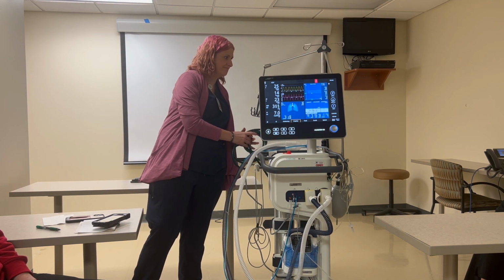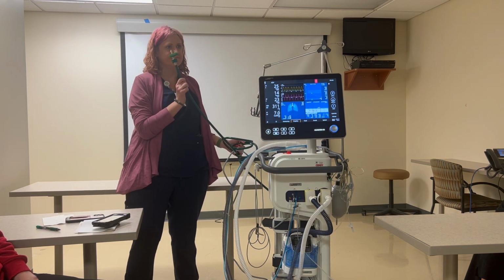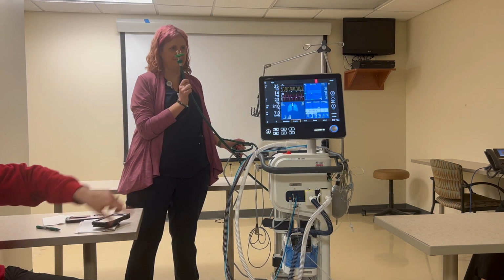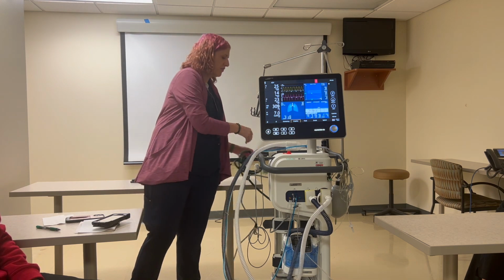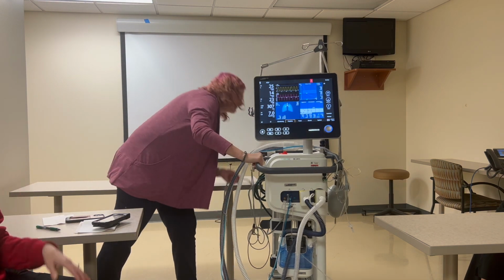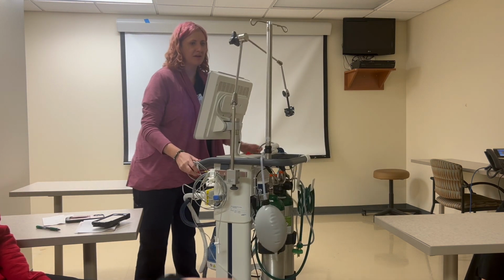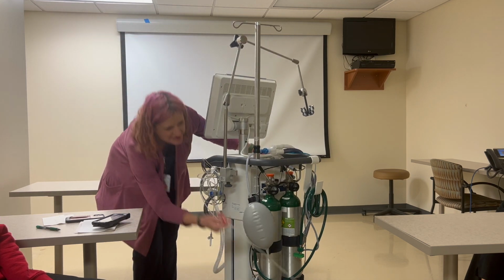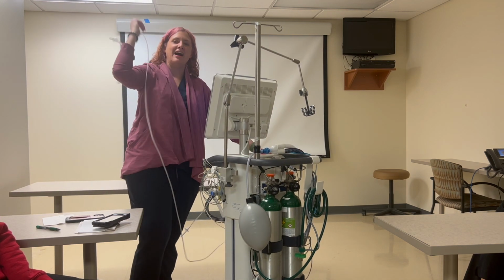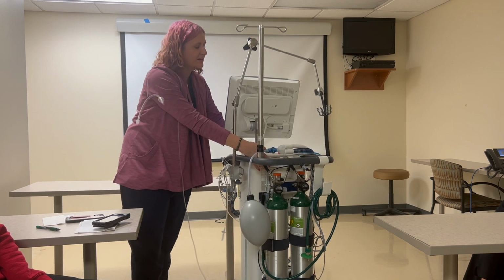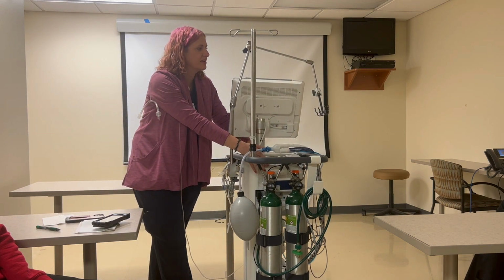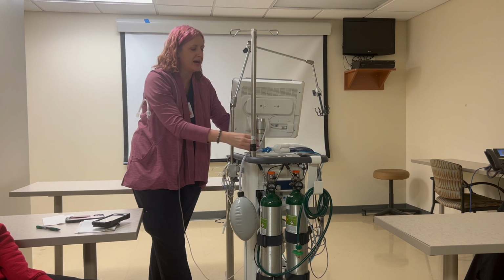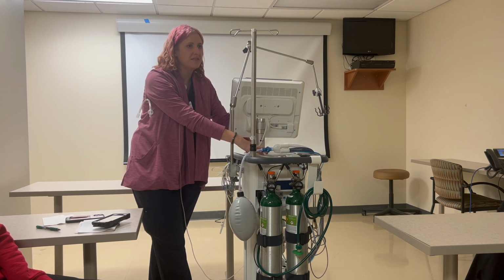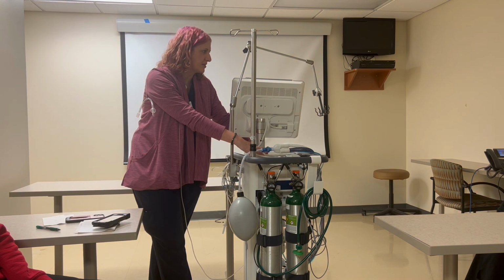Oh, really? So you don't have to plug that in? It's just giving the pressure, so the patient's already getting air? 21% FiO2 is room air. So in the back here is our air entrainment center. The ventilator is pulling in room air from the back. There's a HEPA filter back here. This is how it's delivering room air to our patient, and this is how we get by without having that air hose.